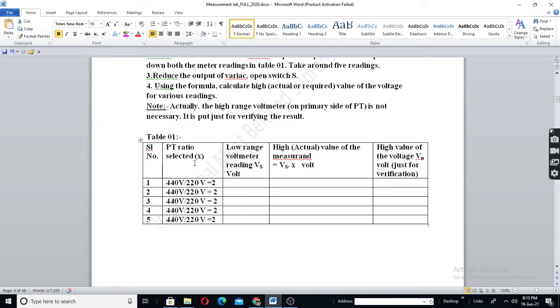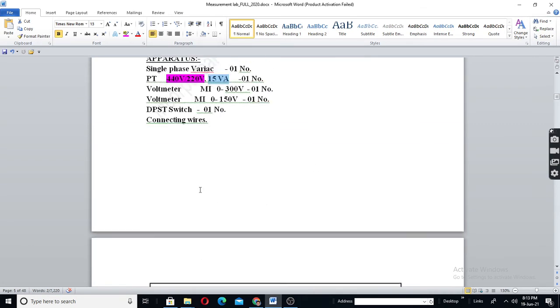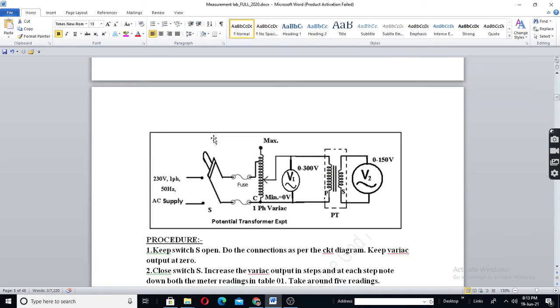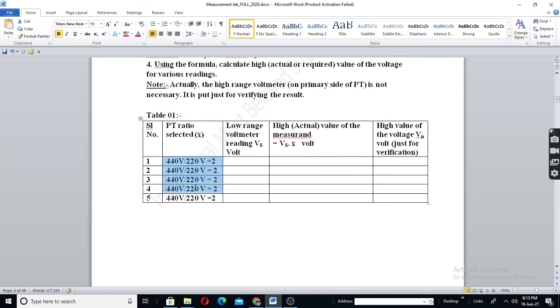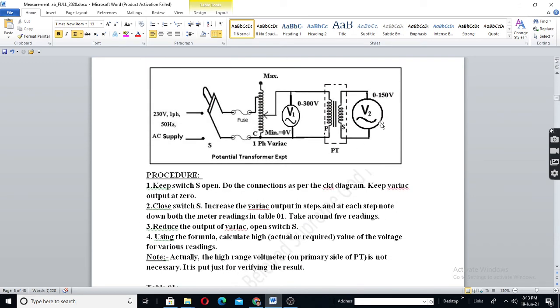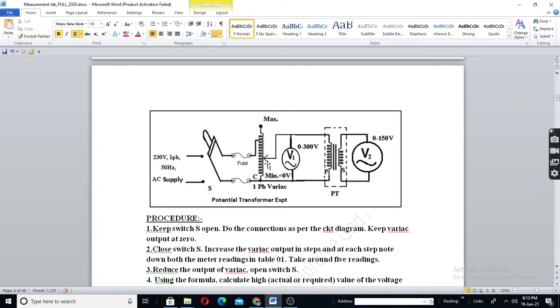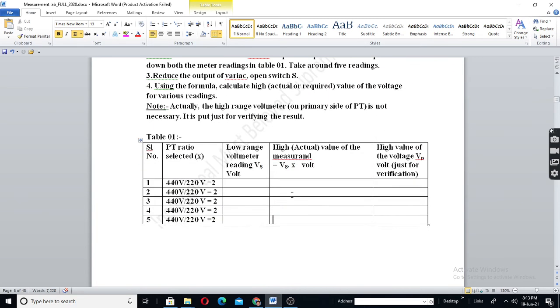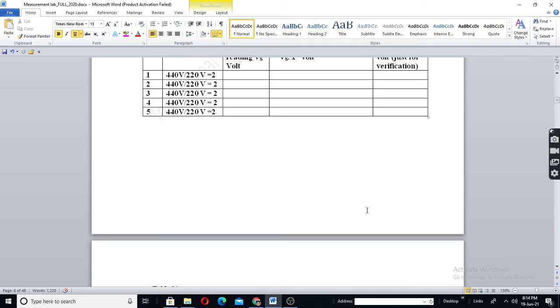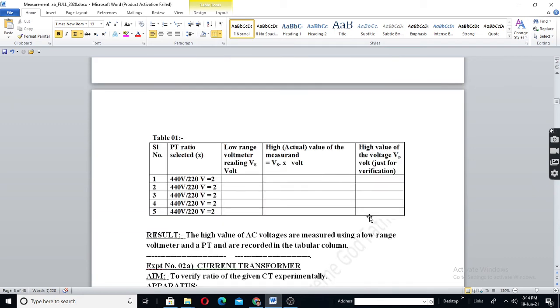The PT ratio is x. X is 2 here. 440 by 220. So, 2. And V2 or Vs, what you measure here, multiply by 2, you will get high value of line voltage. That is the primary voltage. And the secondary voltage is Vs. So, Vs into x will be equal to Vp.